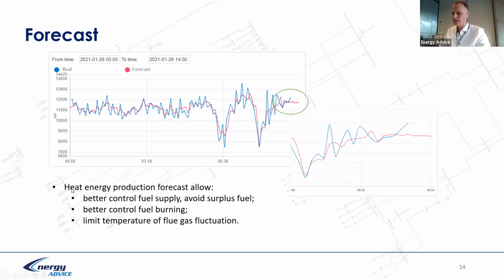But why do we need a heat energy production forecast? Because we have better control of fuel supply and avoid surplus fuel. Simply, we don't push surplus fuel to the furnace, we have better control of fuel burning, of course, because of the limitation of surplus fuel and limited flue gas temperature fluctuation.